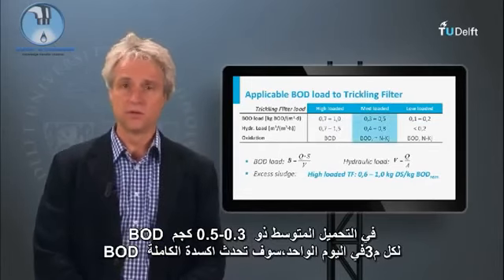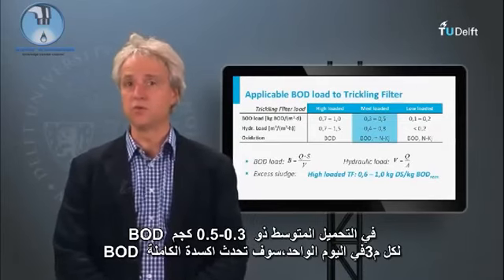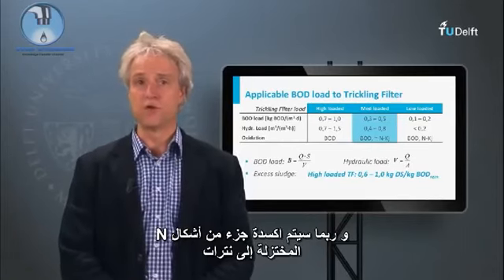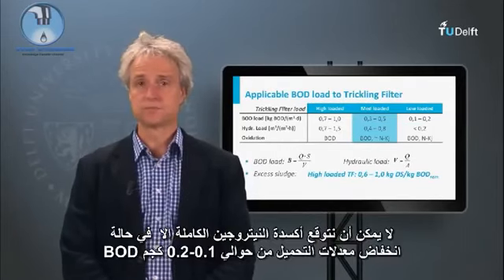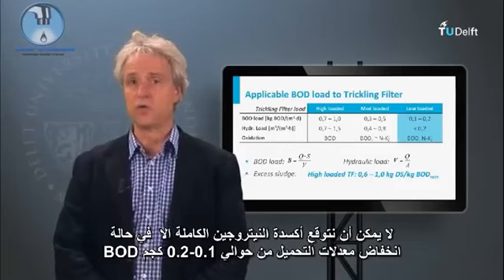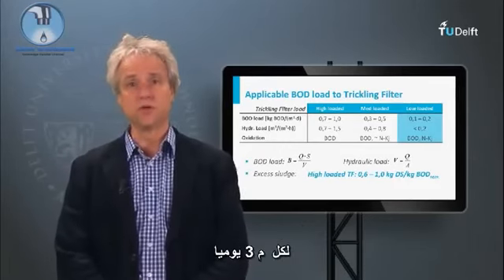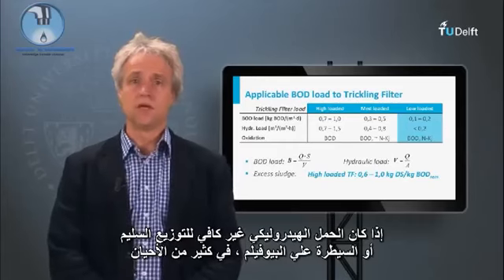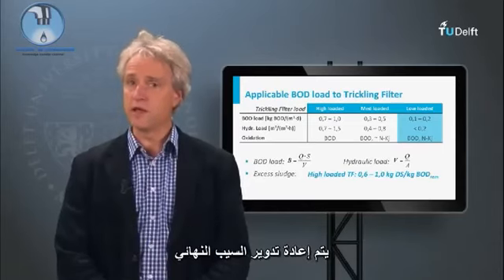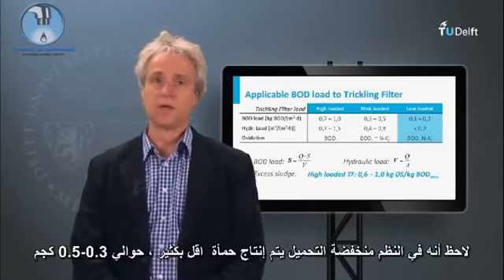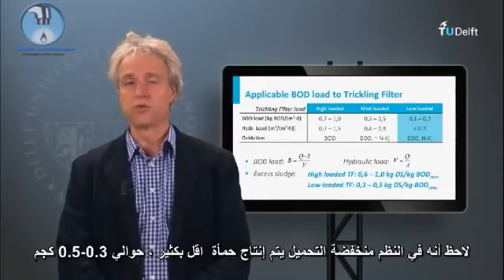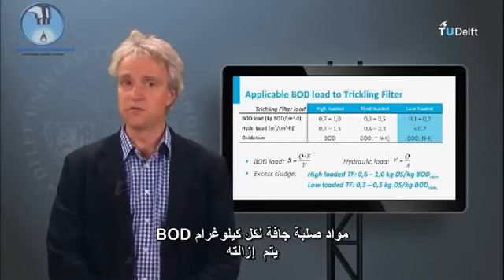At intermediate loading of 0.3 to 0.5 kg BOD per cubic meter per day, full BOD oxidation will occur and part of the reduced N-forms may also be oxidized to nitrate. Full nitrogen oxidation can only be expected at low loading rates of about 0.1 to 0.2 kg BOD per cubic meter per day. If the hydraulic load is insufficient for proper distribution or biofilm control, often effluent recirculation is applied. Note that in low-loaded systems much less sludge is produced, about 0.3 to 0.5 kg dry solids per kg BOD removed.